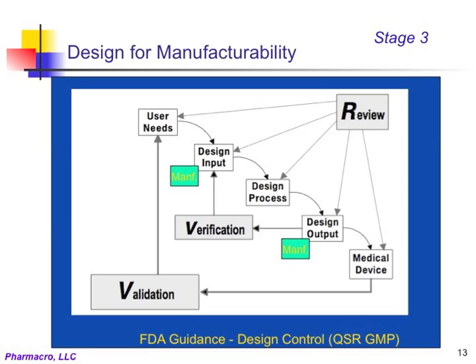In addition to verifying that the device meets the established specifications, it is also tested under conditions of intended use to ensure that the user needs are met and that the user can successfully use the device in a safe and effective manner. This is called design validation, which may involve testing in clinics or in test labs under simulated use conditions. Depending on the device and the intended use, there are specific protocols that may need to be followed in this design validation testing. The design input is an important document that details the specific requirements that the product will need to meet in order to satisfy user needs.